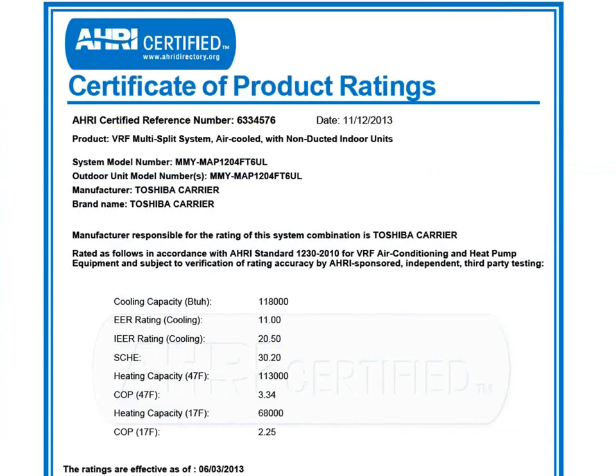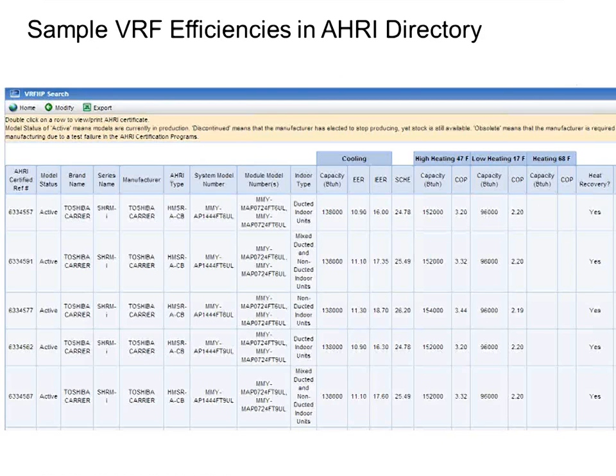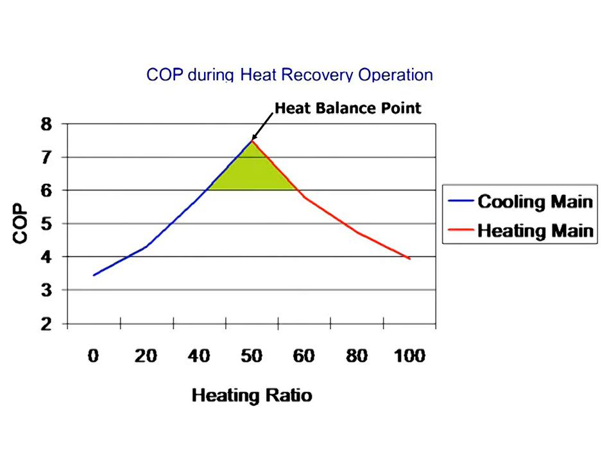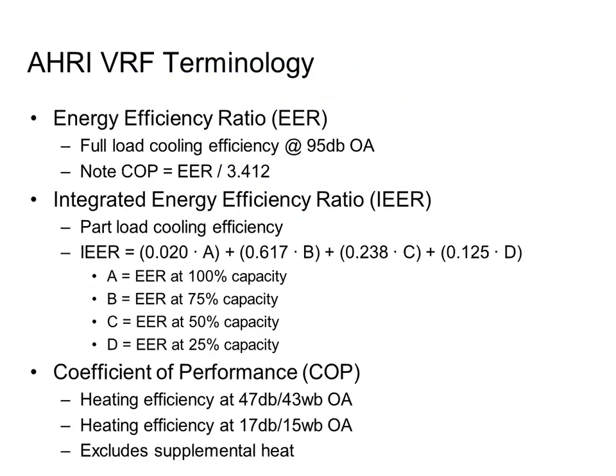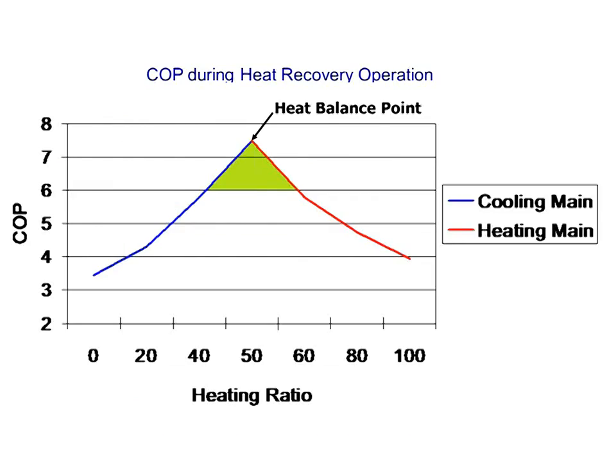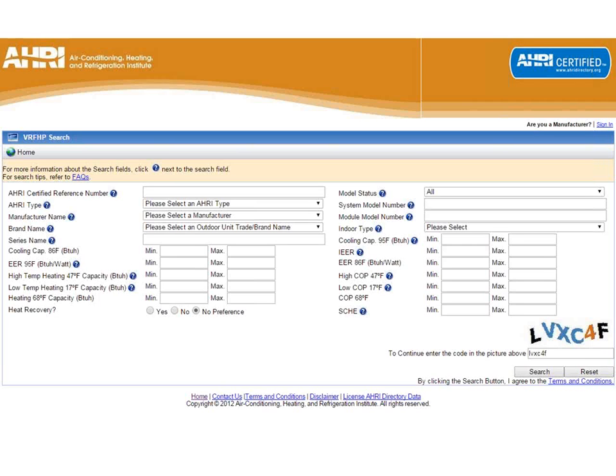Farad asks if you can get an EER rating at various outdoor air temperature conditions for simulation purposes. The answer is probably no. You can't get it from AHRI. If you look at the AHRI table real quick, where'd it go? It does show you cooling capacity and EER at 95 and at 86.